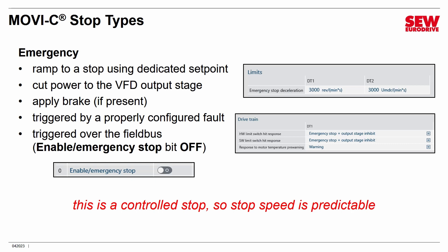The emergency stop is similar to an immediate stop in urgency but behaves differently. Instead of just cutting power, it does a controlled ramp to a stop using a dedicated set point — for example, 3000 RPM per second — bringing the VFD to a predictable stop. The stop time is predictable under normal conditions. It does the ramp first, then cuts power to the output stage, then applies the brake if present. You can invoke an emergency stop by associating it with a fault such as limit switches, or by transmitting the emergency stop bit over the field bus.